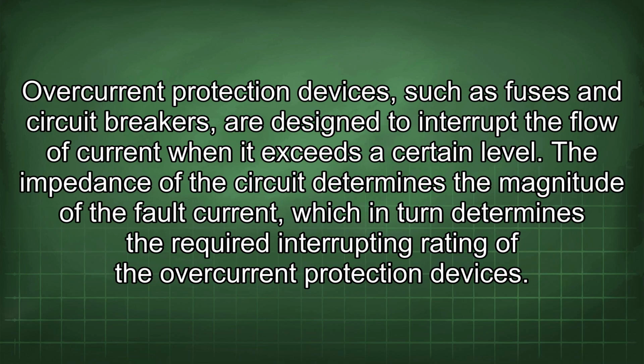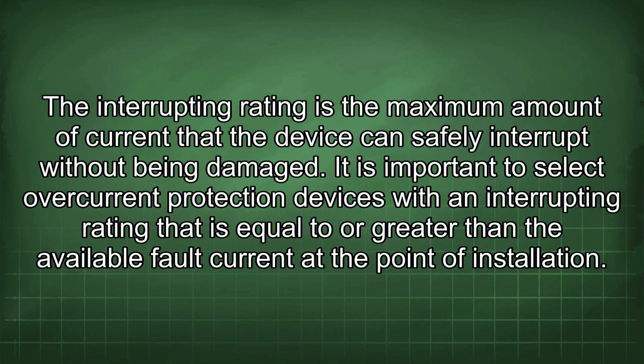Overcurrent protection devices, such as fuses and circuit breakers, are designed to interrupt the flow of current when it exceeds a certain level. The impedance of the circuit determines the magnitude of the fault current, which in turn determines the required interrupting rating of the overcurrent protection devices. The interrupting rating is the maximum amount of current that the device can safely interrupt without being damaged. It is important to select overcurrent protection devices with an interrupting rating that is equal to or greater than the available fault current at the point of installation.